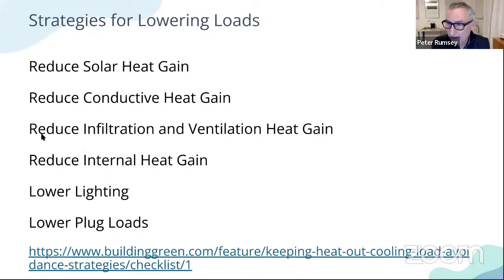Reduce infiltration and ventilation too. When it's really hot and humid outside, infiltration through the building envelope or too much outside air coming in can be bad from a cooling perspective. We do need a certain amount of fresh air as humans, and filters too if you're in the middle of the city, but that fresh air needs to be cooled down, which is another cooling load, the ventilation requirement. So we want to get it right, not too little, but not too much. Many buildings now use CO2 sensors to sense how much air to bring in as CO2 rises, which happens when there are a lot of people in a room, signaling that more fresh air is needed to bring it back to normal. Reducing internal heat gains is another way to lower the loads.